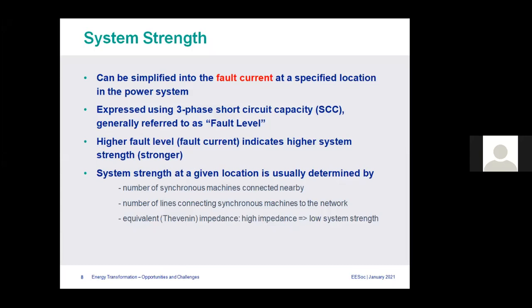And it's obvious system strength at a given location is usually determined by this: if we have a number of synchronous generators nearby, the fault level will be high. If you have long transmission lines, the fault level will be low. And if you have multiple lines in parallel, the fault level will be high again. So the system strength is similar. Or effectively, in theoretical or mathematical terms, it's the Thevenin impedance. High impedance means a lower system strength or lower fault level. The other way around, if you have a very low impedance from the source to the point, then it will be a higher system strength location.